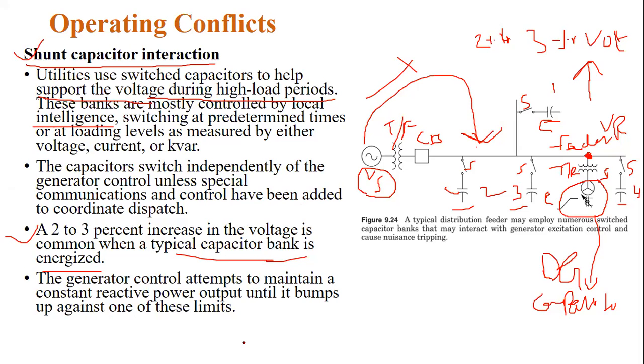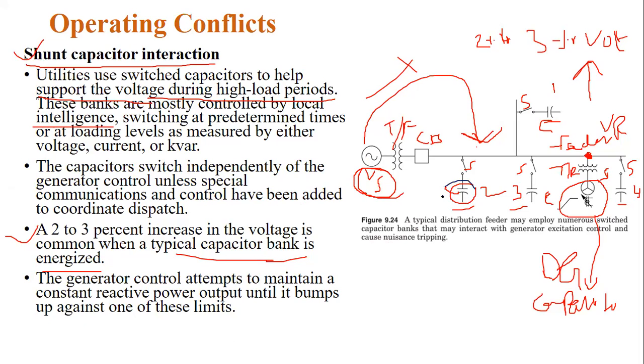Now, what is the main thing here? As I said, these capacitor banks are operating independent of the source, nothing but the generator. So what will happen here? The generator control attempts to maintain a constant reactive power output until it comes up against one of its limits. Here, what is the meaning of this? Please wait for a second.